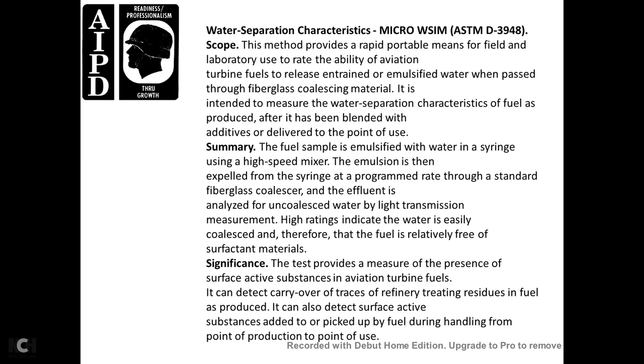Water Separation Characteristics — Microseparometer (MSEP), ASTM D3948. Scope: provides a rapid, portable means for field or laboratory use to rate the ability of aviation turbine fuels to release entrained and emulsified water through a fiberglass coalescer. Summary: a fuel sample is emulsified with water using a high-speed mixer; the emulsion is expelled from a syringe through a standard fiberglass coalescer; the effluent is analyzed for uncoalesced water. High ratings indicate water easily coalesces and the fuel is relatively free of significant surface-active material. Significance: provides a measurement of the presence of surface-active substances in aviation turbine fuels.